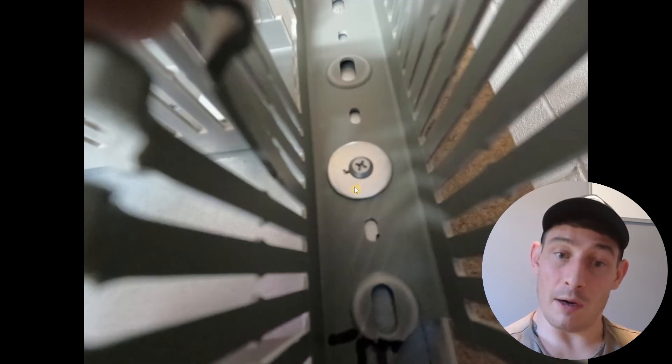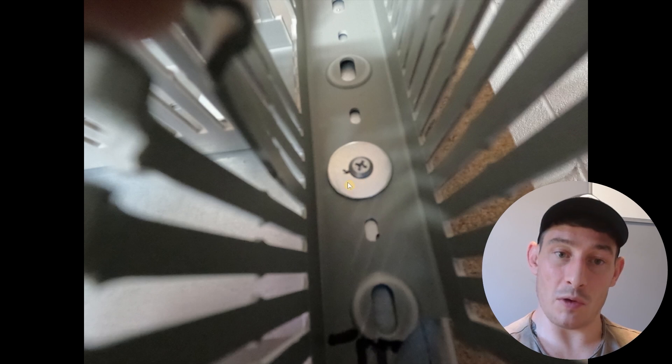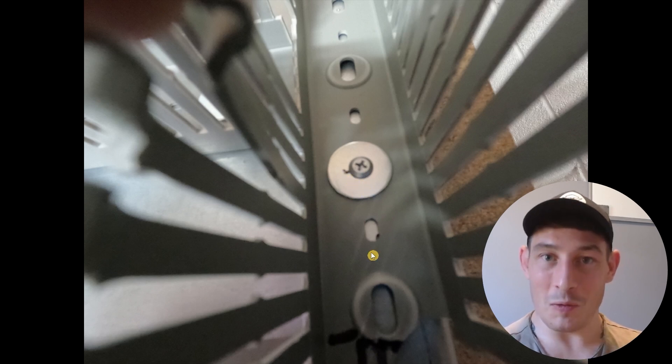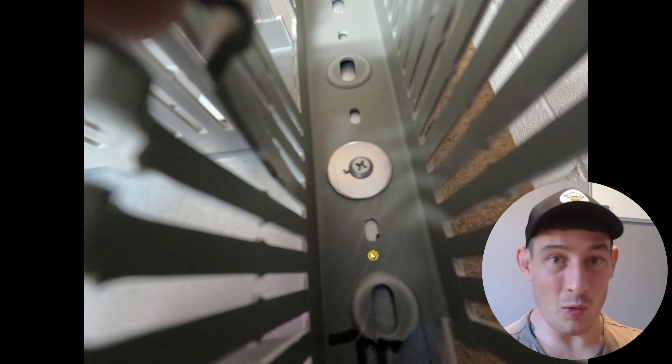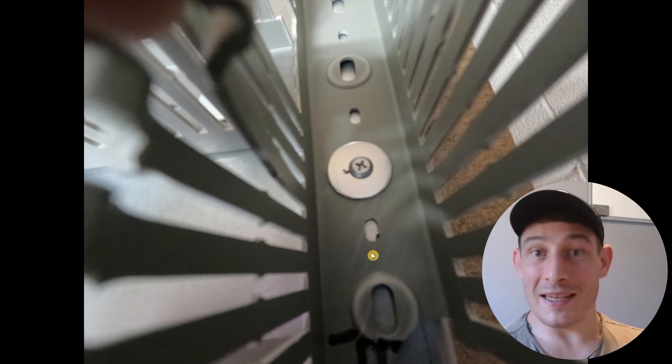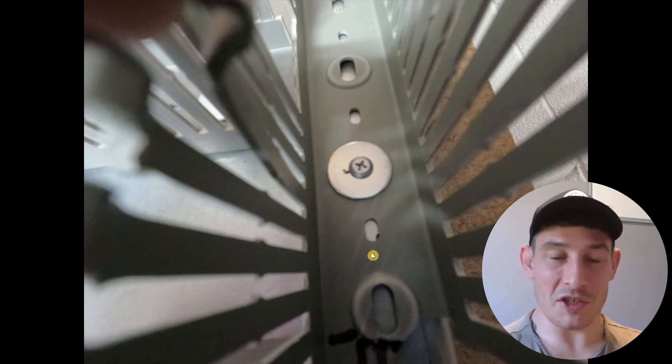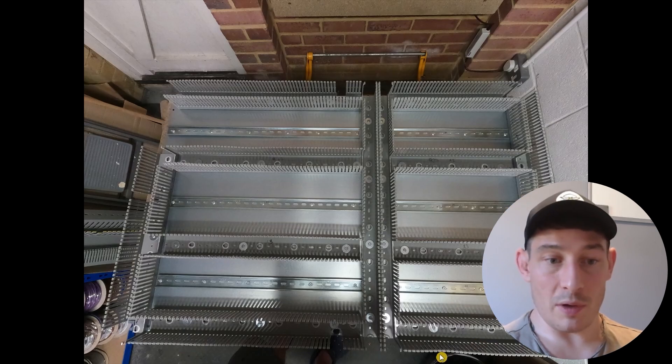And here's what I mentioned earlier about a bit of burr underneath the tech screw, so just make sure you go around and visually check and remove any of those little burrs. Those will definitely cause issues when you come to test later on or even years down the line could potentially cause issues. So there we go, that's what it looks like when it's all finished ready for the components.